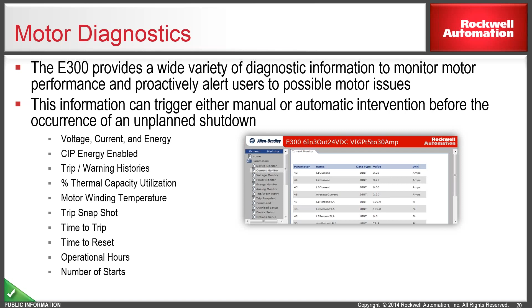So the add-on profile, the AOP profile for Studio 5000, is a single software for the controllers and also for the relays. You don't need a separate software for it. You can directly configure it. You can import the profile of E300 into the controller itself, and you can do the programming. Add-on instructions are also available.